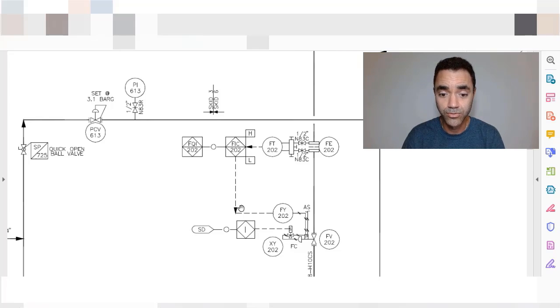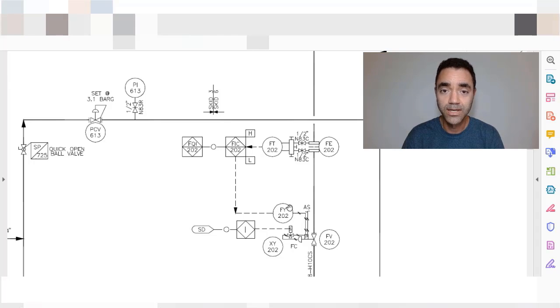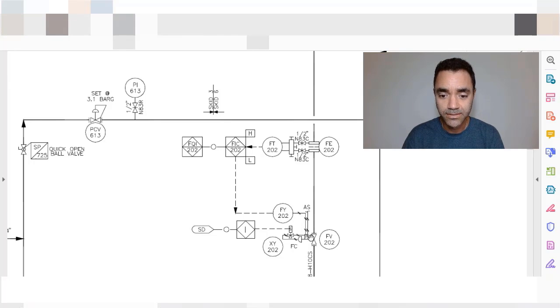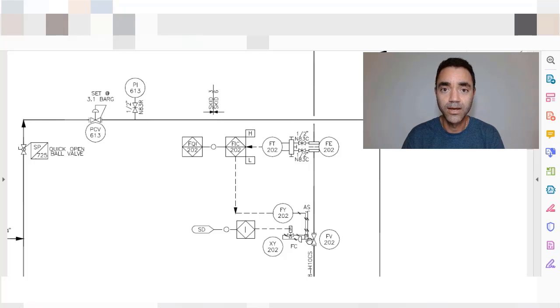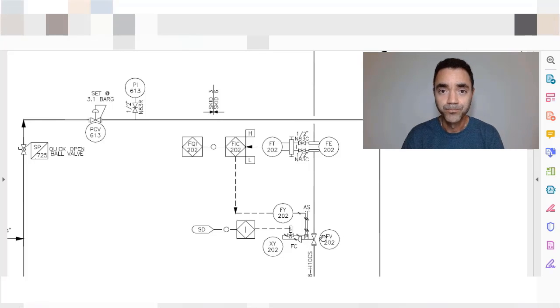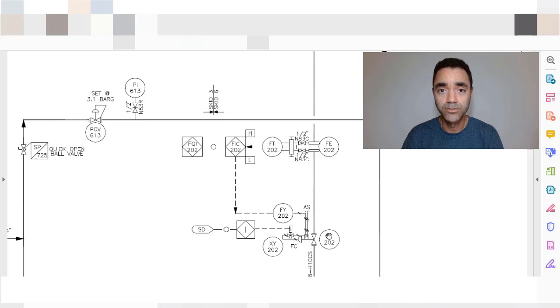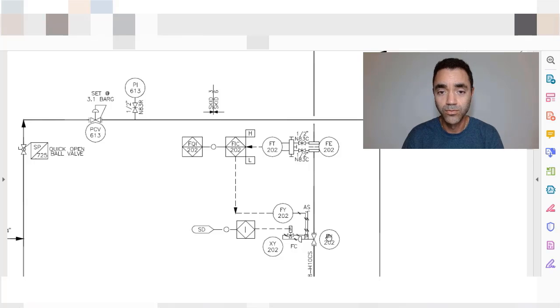That sends to a converter, a signal converter that goes to the actuator of the control valve. This is a FV, flow valve. In some cases you can find this nomenclature as FCV or flow control valve.